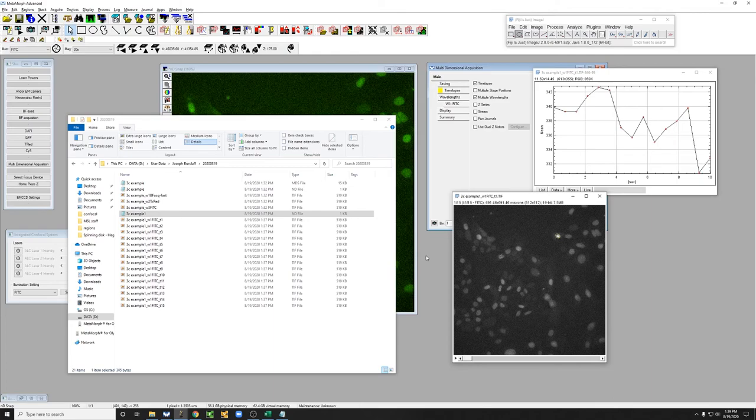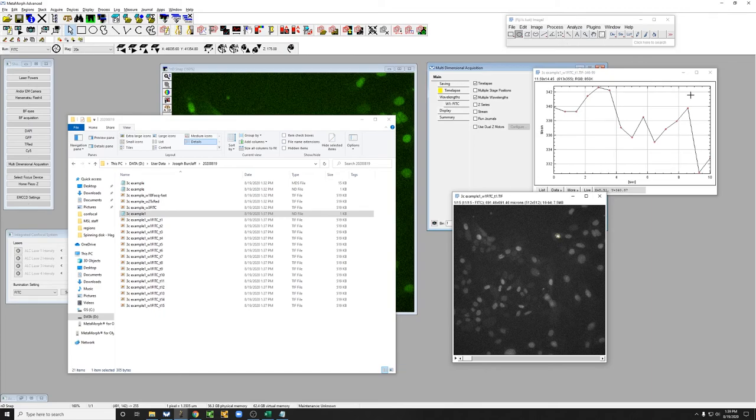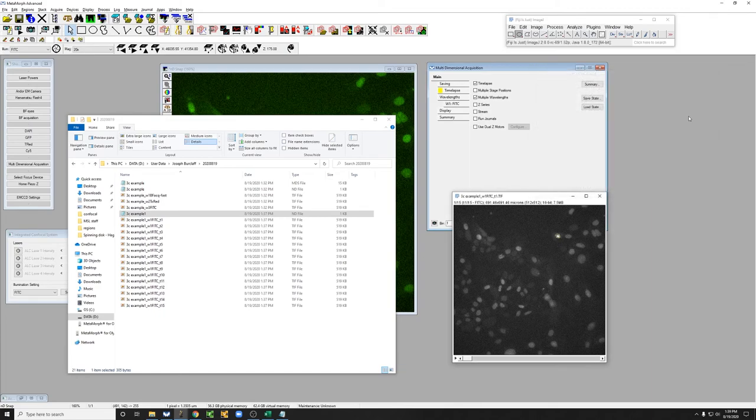So if that relative position of cover slip and objective drifts due typically to thermal fluctuations, the hardware autofocus will compensate for that. Now it's not going to compensate for changes in your cells' positions relative to the cover slip, for example if they ball up or crawl into a matrix, but at least it will deal with thermal fluctuations when you're running an experiment.